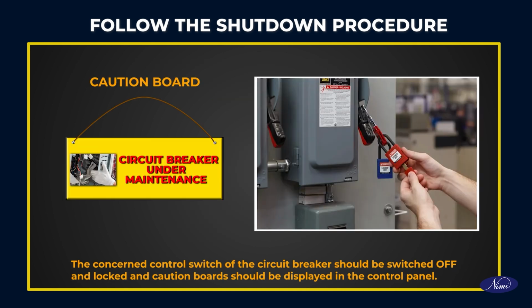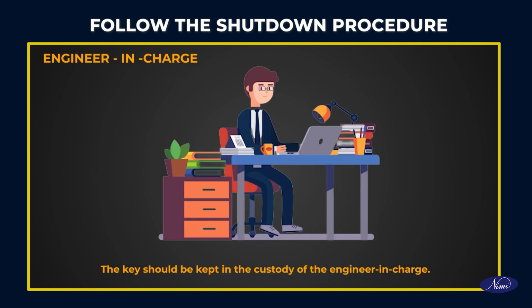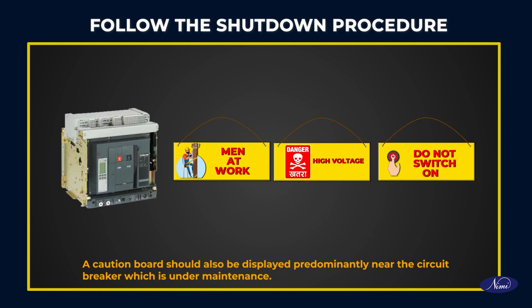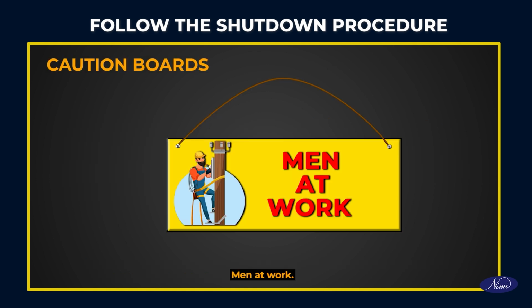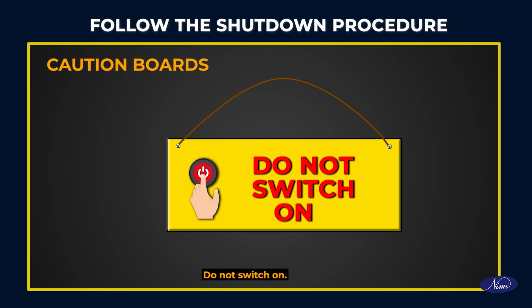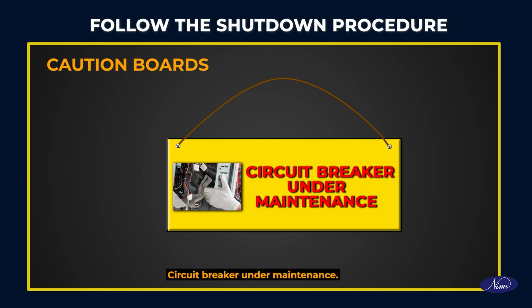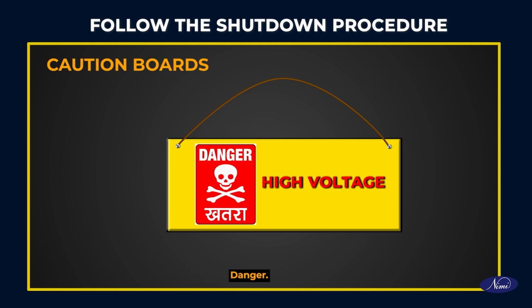The concerned control switch of the circuit breaker should be switched off and locked and caution boards should be displayed in the control panel. The key should be kept in the custody of the engineer in charge. A caution board should also be displayed prominently near the circuit breaker which is under maintenance. Caution boards: men at work, do not switch on, circuit breaker under maintenance, danger.